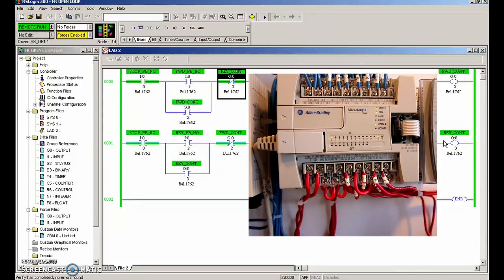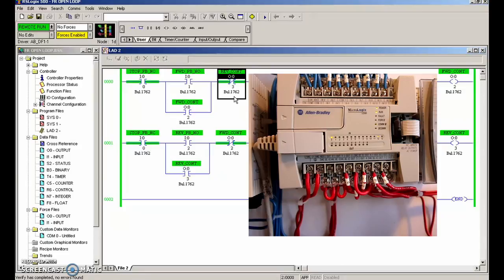So the three ways that I found that myself and others will screw up in the shop: first, the IO configuration is not done so you get the fault light; second, you put the wrong address or wrong instruction in, or screwed up your program logic; and third, the wiring — you forgot to wire up one of your outputs or forgot to jumper your commons back to the source. That's it, we'll see you on the next video, hopefully this helps to get you through each of your projects.